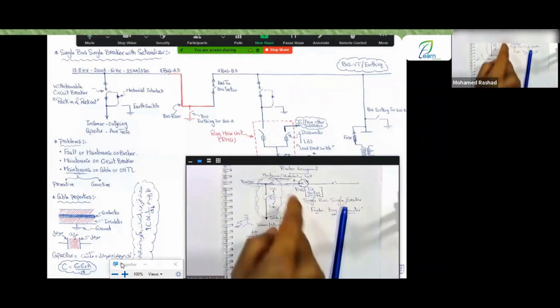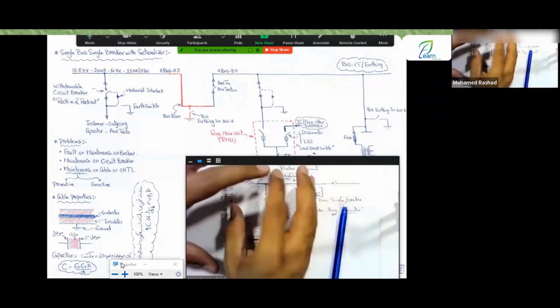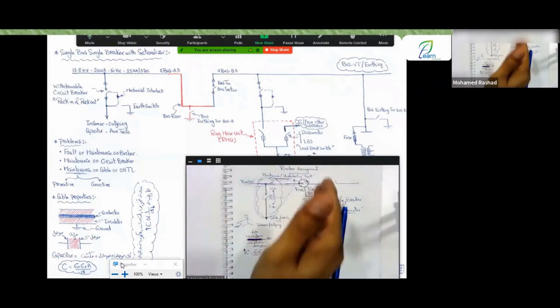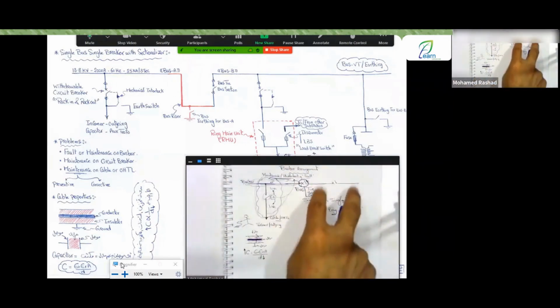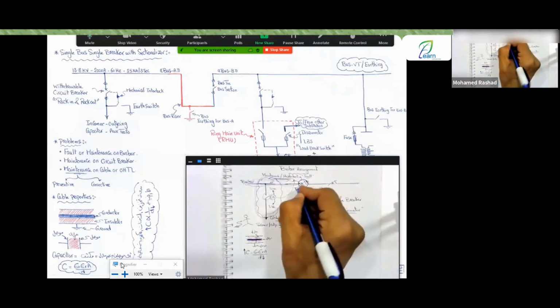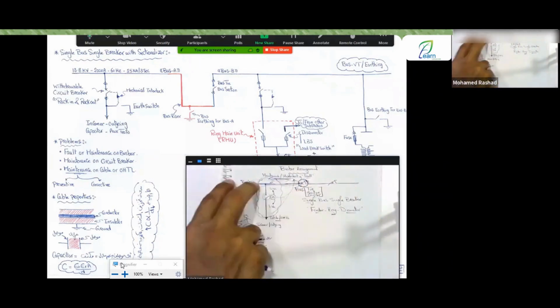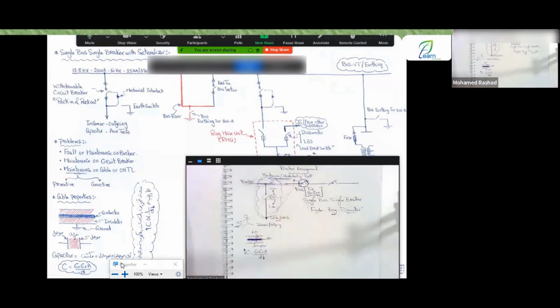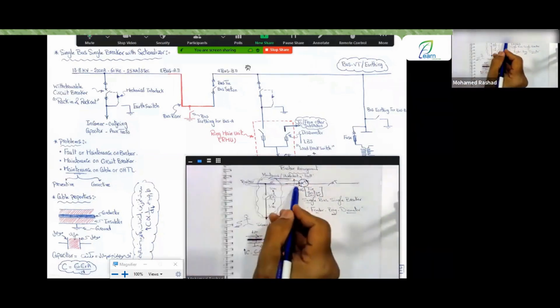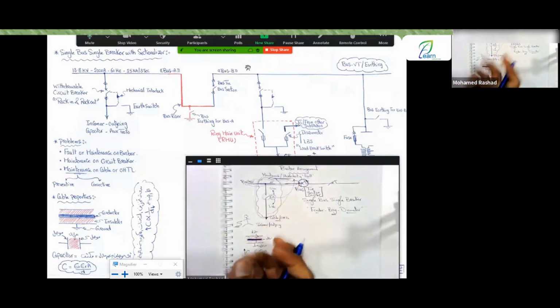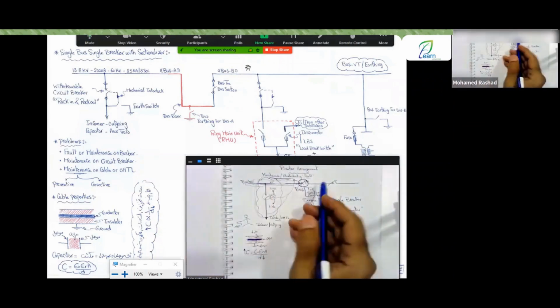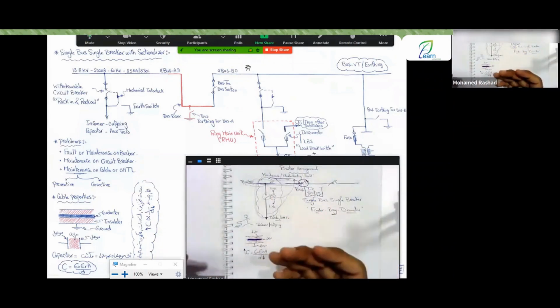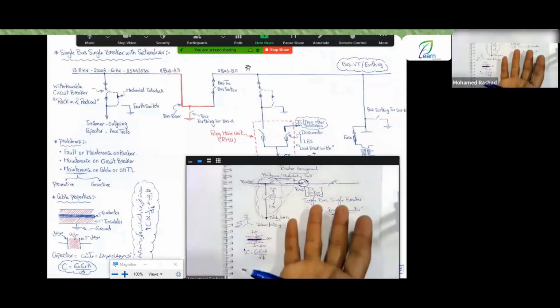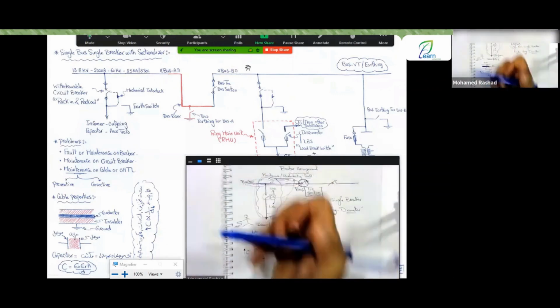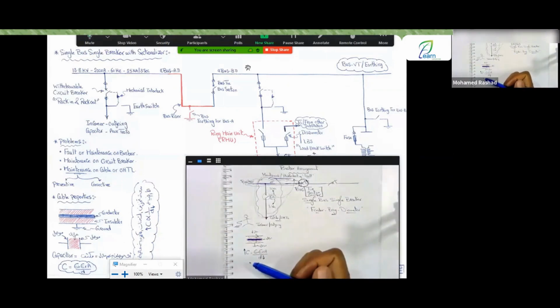This way, if one of the bus bars has its source go out of service, the source here can share, or these 2 together can close this breaker and that breaker, so these 2 can share the loads of the 3 bars. Or it could be that one of the bars has a very heavy load on it, while the other 2 bars have some loads disconnected, resulting in a lighter load. So what's the problem with letting them share their power with the 3rd bar?